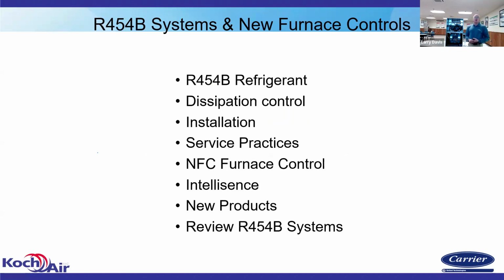What we're going to talk about today is 2 different categories, but we're going to combine them together. We're going to talk about the new products that have the Puron Advance, which is Carrier's brand for the R454B refrigerant. We'll talk about what some of the similarities and differences are for that refrigerant compared to the 410A. Because of that refrigerant and its flammability classification, we have to have a means to monitor for leaks, and we have to have a process to mitigate an issue if there is a leak. That's our dissipation control. You'll see that information a lot through both presentations.